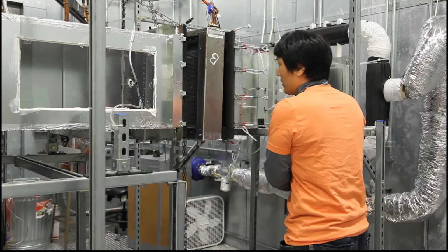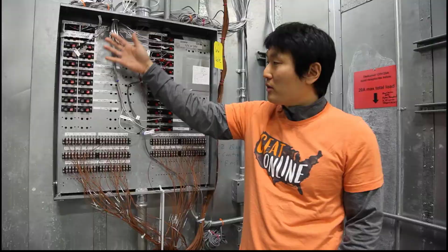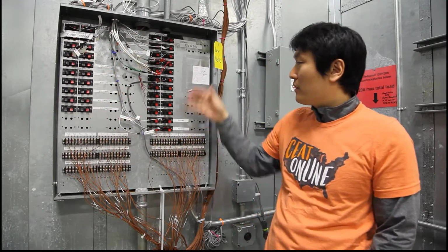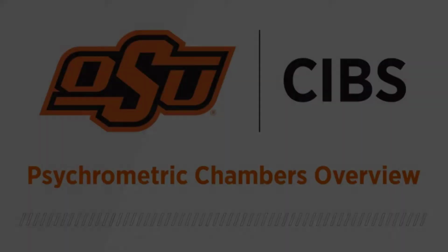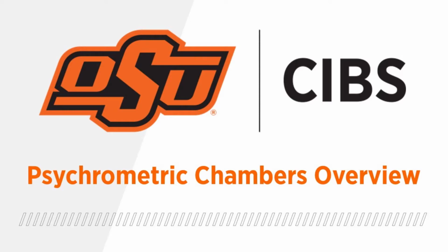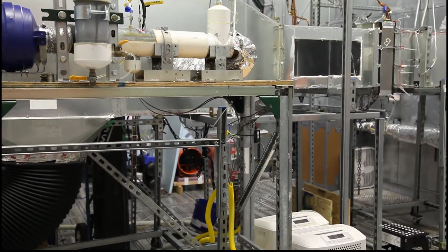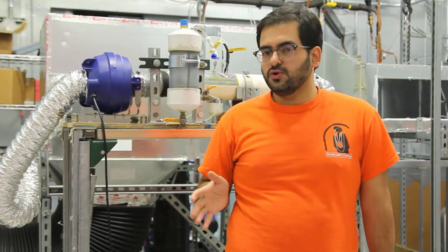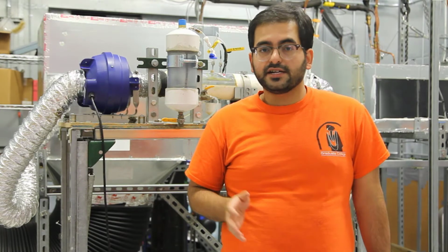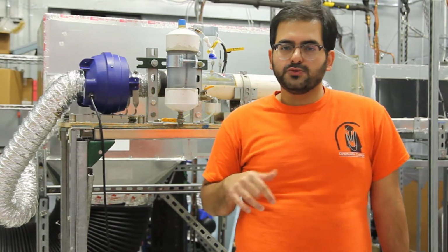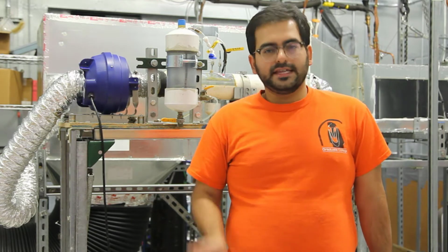We've used these pair of rooms for a plurality of projects, including unit testing, component testing, and everything in between. So we're really excited about how these facilities can be used to support CIBS as we move forward. The chamber is split into an outdoor room and an indoor room. Currently we are standing inside the outdoor room, while on the other side is the indoor room. This makes sure if you want to test a split unit air conditioner or heat pump, you can keep the outdoor unit in the outdoor room while you keep the indoor unit in the indoor room.